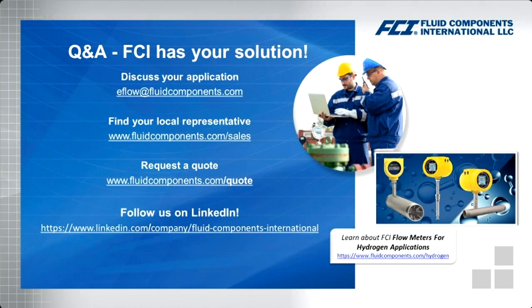So those do exist. However, I know that sometimes when you're installing a meter in the field in those kind of applications, those ideal flow conditions don't often exist. So in those cases, what we would use is a flow conditioner prior to our meter. That would change those requirements to a 3 up and 3 down from that flow conditioner. And for your best accuracy when you're doing that, we also do recommend that if you're going to use flow conditioning, that the meter itself be calibrated with that line meter in the same flow line during the calibration process on your actual gas.